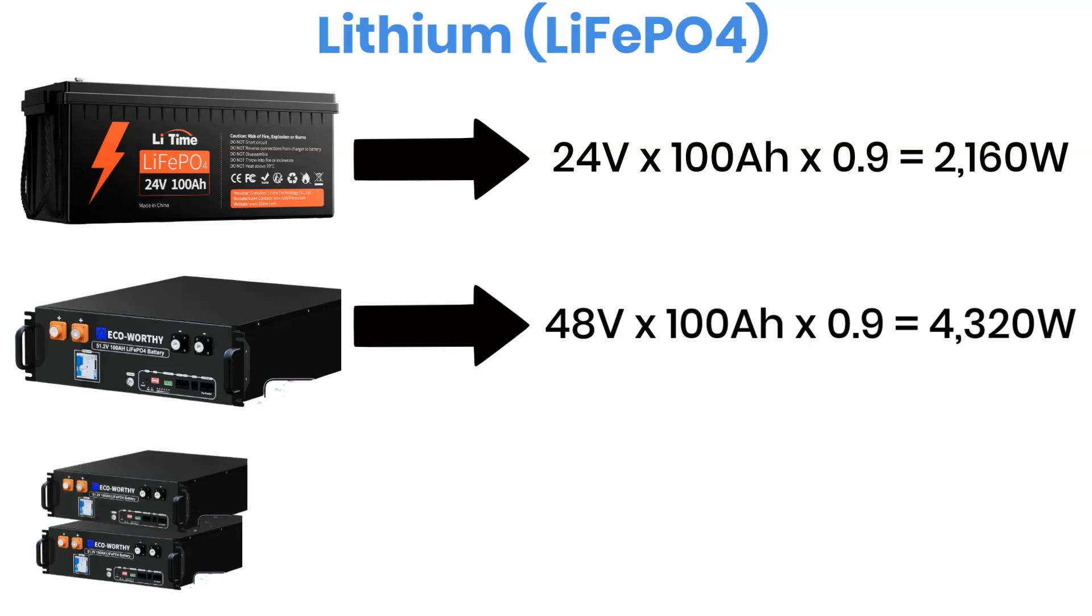Now, if you connect two 48 volt 100 amp hour batteries together, forming a 48 volt 200 amp hour bank, you can handle up to around 8,000 watts.